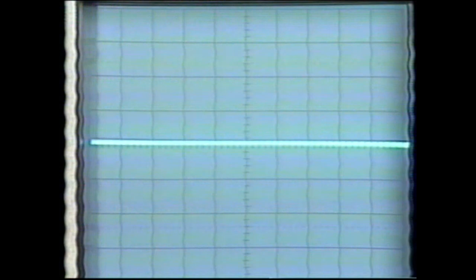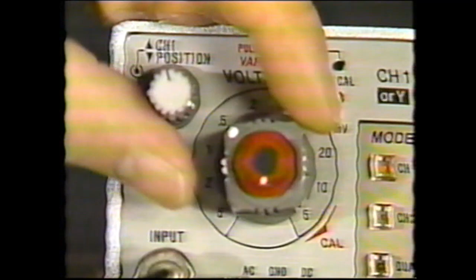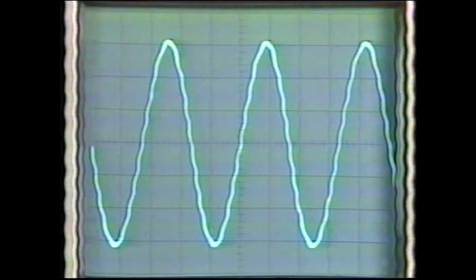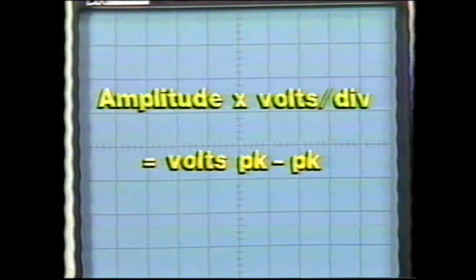The vertical position controls allow the operator to position the signal anywhere on the Y-axis. This makes voltage measurements and signal comparison easier. The vertical attenuator pertains to the voltage per centimeter or vertical division on the CRT graticule. By changing the attenuator position, the voltage values on the CRT display are changed, thereby enlarging or attenuating the signal on the CRT. The vertical attenuator can be used to make voltage measurements.